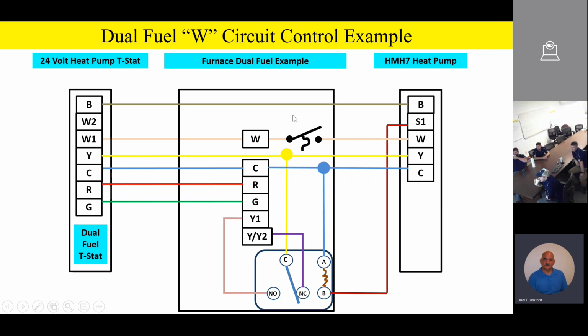And so let's walk through what this is going to do. Typically, when the outdoor unit calls for heating operation and the switch is open electrically, it's going to keep the furnace from coming on as long as that suction line is above 65 degrees. Now, when we go to defrost, remember team, the heat pump is going to go into the cooling mode of operation during defrost to defrost the outdoor coil. When it goes into defrost, that suction line is going to get cold.